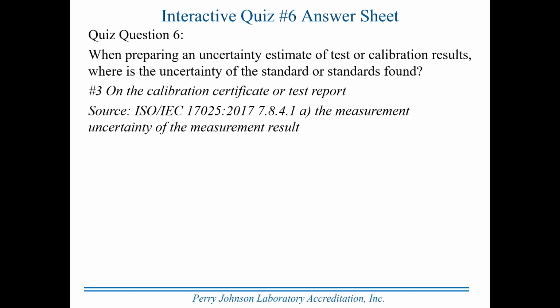There was then the caveat based on ILAC P14 that if the equipment calibrated would be used in itself to perform calibrations, then it had to be on the certificate. They've taken care of that issue in the 2017 version of the standard by saying, regardless, the measurement uncertainty always has to be on the certificate, always. So as you're operating under the new standard and preparing test reports or calibration reports, for test reports where you had to estimate the uncertainty, it didn't apply if the uncertainty is factored into the acceptance criteria. But if the uncertainty has to be estimated for a test result, and it always has to be estimated for a calibration result, in both cases, it would have to be on the calibration certificate or the test report, regardless of how that particular instrument was going to be used. So it always has to be on the calibration certificate.